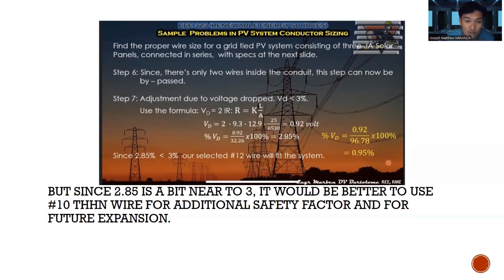So VD, substitute lang natin, 2 times 9.3 times 12.9 times 25 over 6,530 is equals to 0.92 volt. So sa percentage, VD is equals to 0.92 over 32.26 times 100%. So makukuha na natin siya ng 2.85%. So sabi nga, VD is equals to 0.92 over 96.78 times 100 is equals to 0.95%. Since 2.85 is less than 3%, our selected number 12 wire will fit the system. So sabi nga, since 2.85 is less than 3%, ang gagamitin natin dyan is 12.